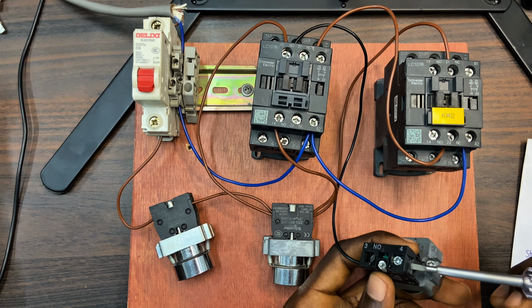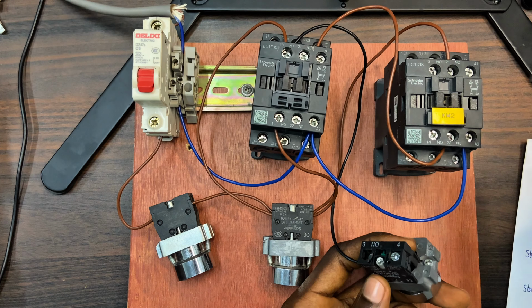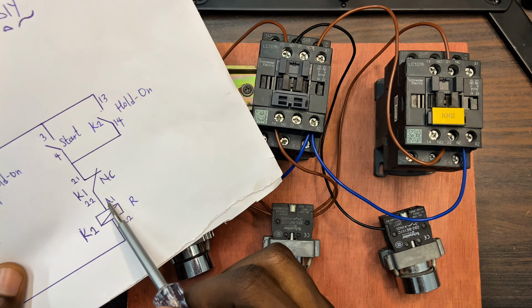And we have to connect a cable from 4 to A1 on the reverse contactor. And before this cable reaches A1, it's supposed to pass through the forward contactor normally closed before it will come to the A1 on the reverse contactor. That is the interlocking. You could see that we have the number 4. This is the start push button for the reverse contactor. We have the live connected from 13 to number 3. And from 4 to 21, that is the normally closed contact on the contactor number 1. That is the forward contactor. From 4 to 21, and then we pick it from 22 to the A1 on the reverse contactor.